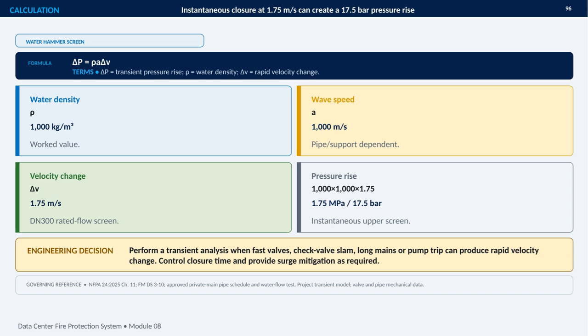This is an instantaneous upper screen value, not a substitute for a project-specific transient model. The engineering decision is to perform a transient analysis when fast valves, check valve slam, long mains, or pump trips can create a rapid velocity change. From there, control closure time and provide surge mitigation as required. The final assessment should use the governing references, approved pipe schedules, water flow testing, and the actual valve, pipe, and mechanical data.